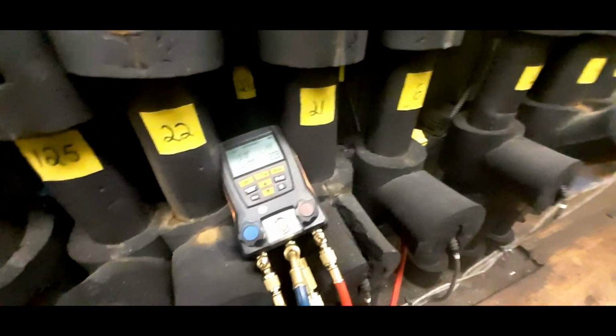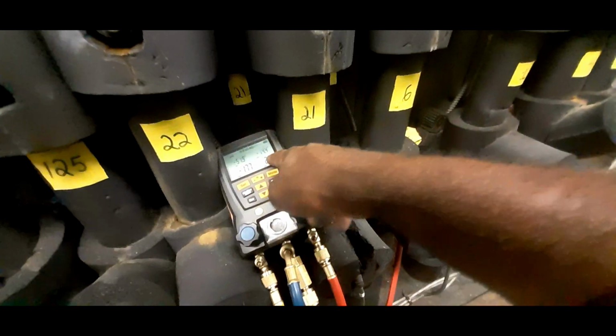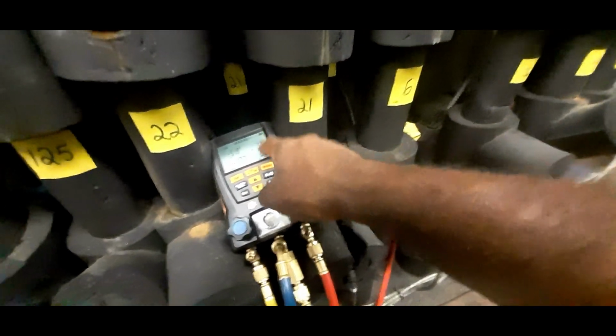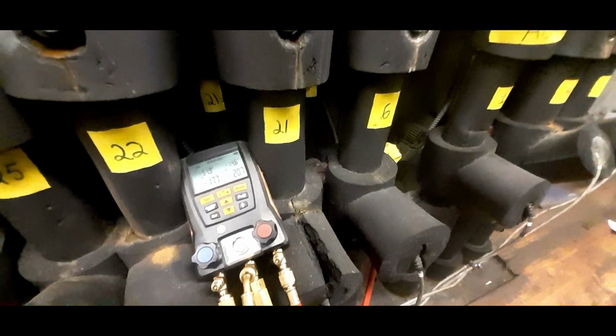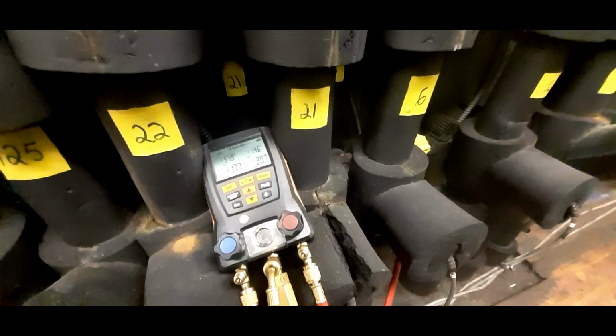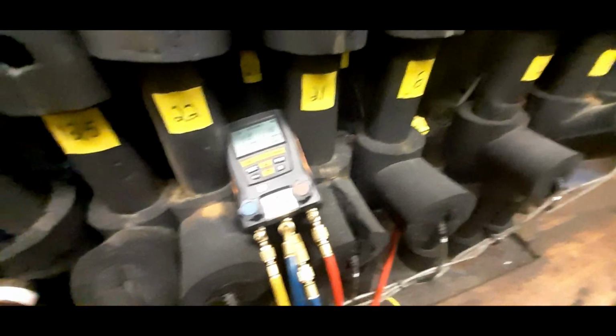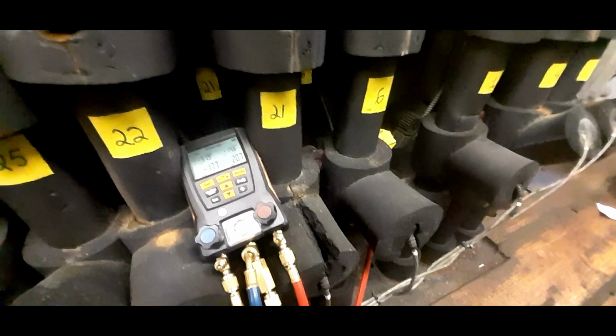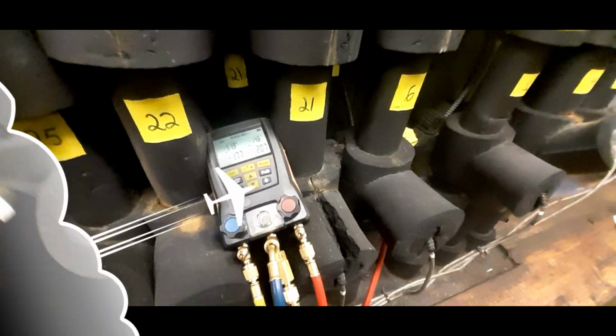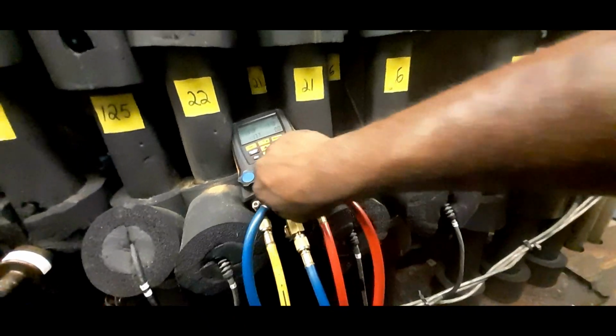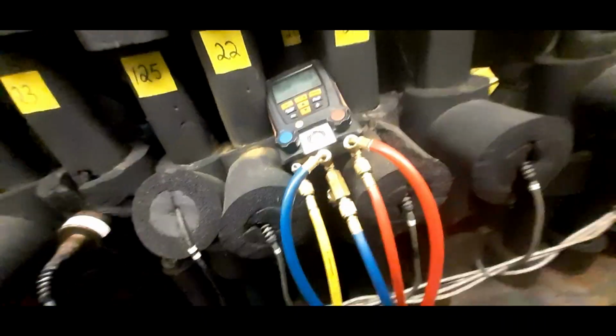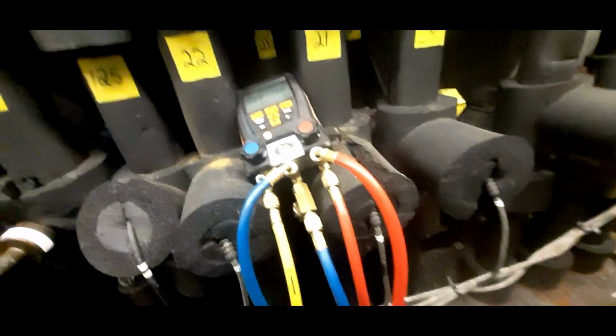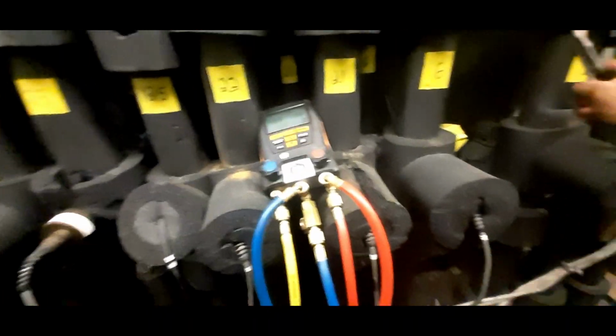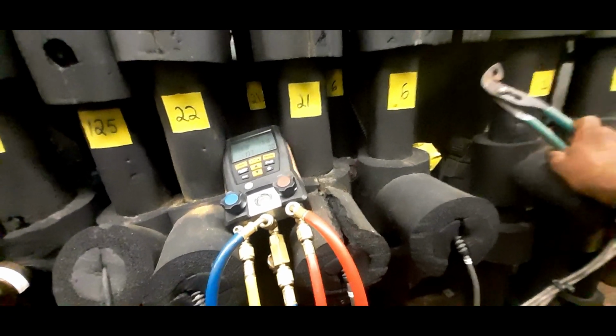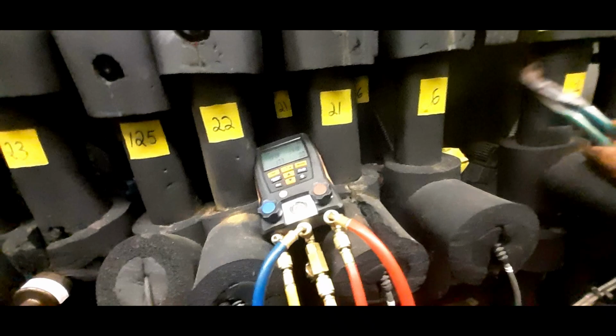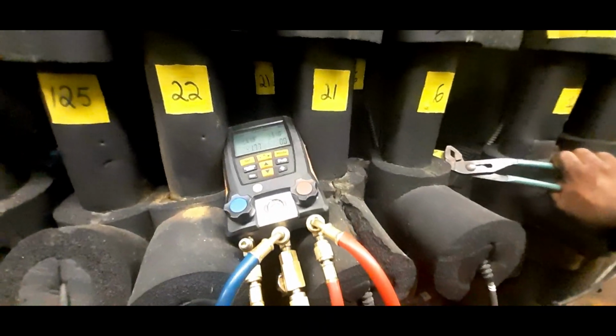These units are designed with a 10 degree TD. So whatever it reads here, when you convert your pressure over to a temperature, the lowest this circuit should be able to go down to is 10 degrees above that. So at nighttime we did see it go down to negative 4 in the freezer, but not the ice cream case. So I'm still gonna go down there and check my TXV screen, make sure we got airflow. Maybe if it's just the screen, I can clean the screen and it can get us by, get us out of alarm. If not, I'll be making a call to the manager. But let's jump into it.